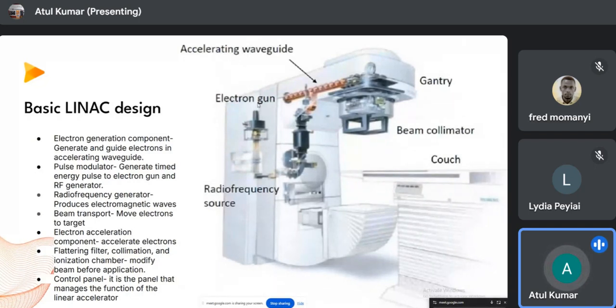There is an electron gun which produces those electrons for us, and then the electrons are injected inside the cavity called the waveguide, or accelerating waveguide. That waveguide is already fed with a radio frequency, usually 3 gigahertz or so. That energy is used to accelerate the electrons. The RF wave accelerates the electrons. The electron beam then hits a target here after bending through a magnet. It hits the target, and that target produces X-rays.